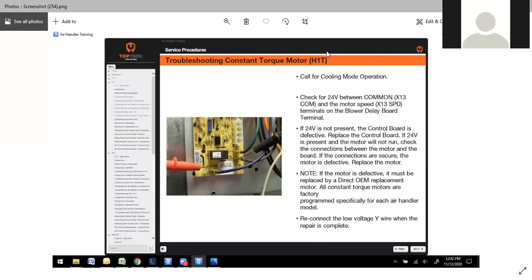So this kind of comes into play with any X13 motor. Your line voltage, whether it's a furnace or air handler, is always present. You're looking for the 24 volt signal to turn on and command the motor and to run at what speed. So if the 24 volts is there, bad motor. If it's not there, bad board.